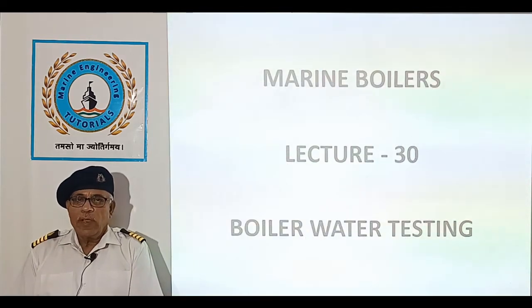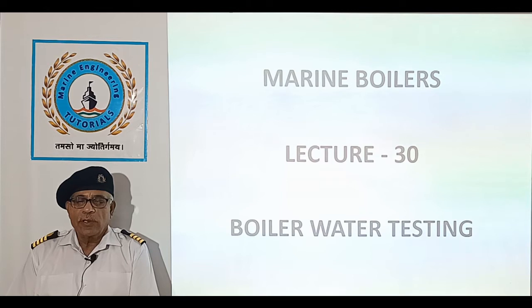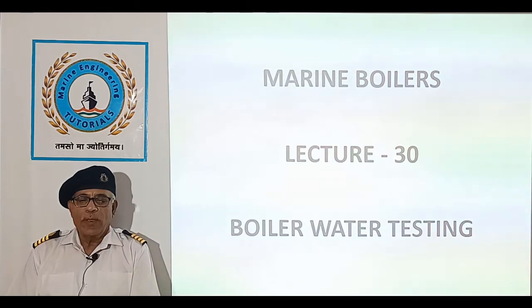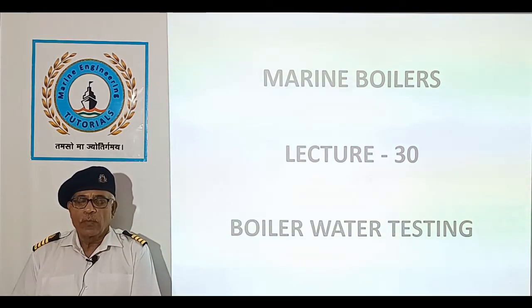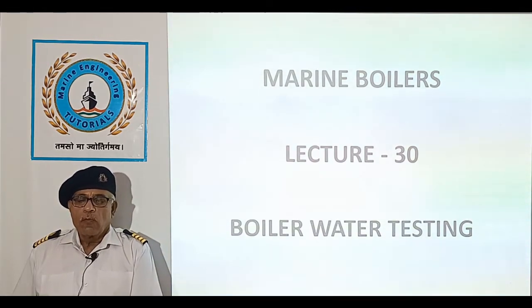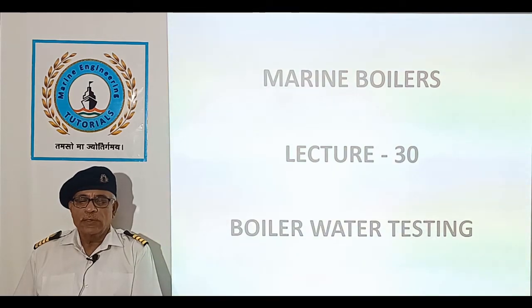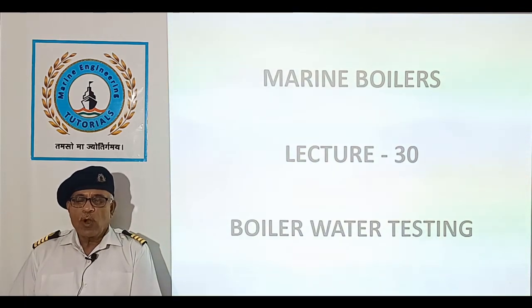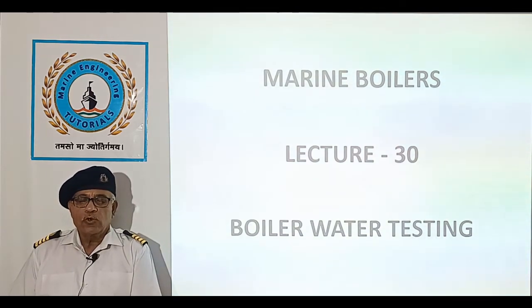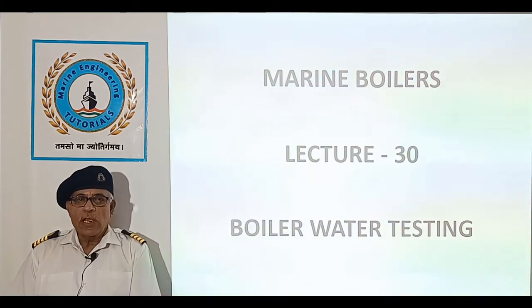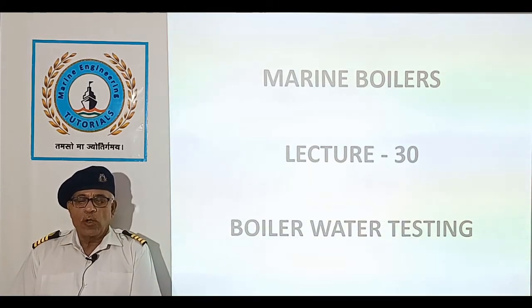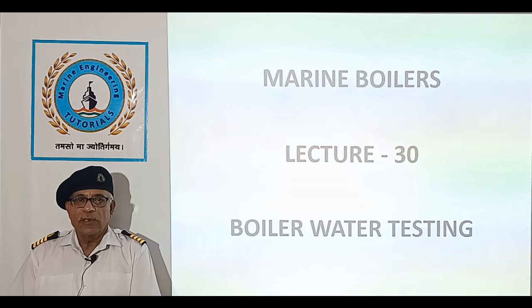Today we have the 30th lecture and the topic is Boiler Water Testing. For reliable operation of water tube boilers, boiler water testing should be carried out daily. In case of smoke tube boilers, weekly testing is acceptable.